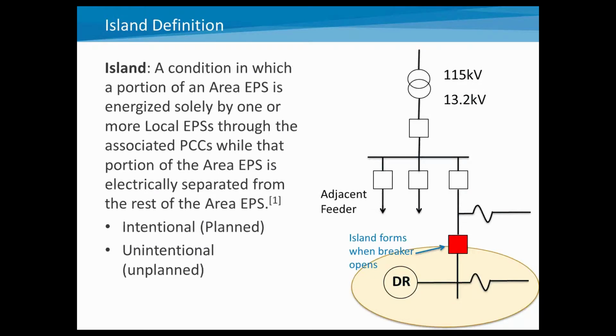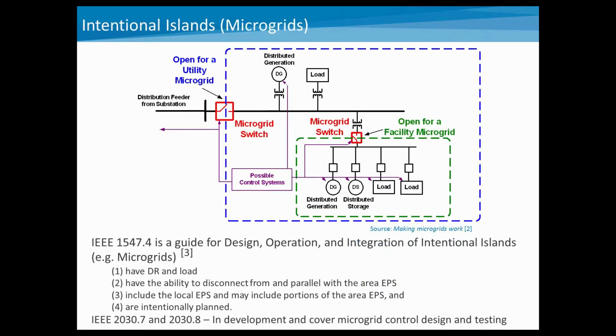It's a condition in which a portion of the area electric power system is energized solely by local EPSs through an associated point of common coupling. So if you look at the figure on the right-hand side, you can see a breaker would potentially open, and since that has distributed resources and load in there, you could form an island. Now, inside of 1547, they mention both intentional islands, or planned islands, and unintentional islands. So we'll talk about those.